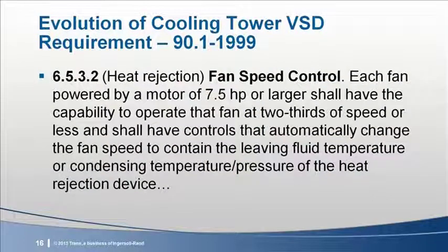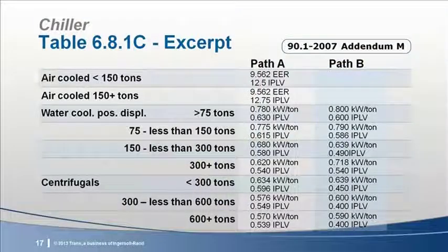Simply put, chilled water pump VFDs are prevalent today. Beginning with 90.1 1999, fan speed modulation was required for cooling tower fans 7.5 horsepower and larger. Often, VFDs were used to comply. Starting in the 1990s, variable speed drives began to be applied to chillers. From a standard perspective, 90.1 2010 added an additional compliance path for chillers.